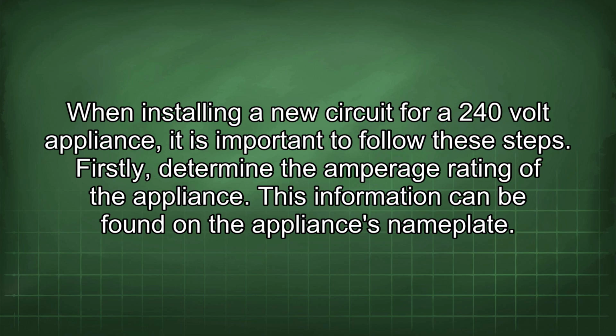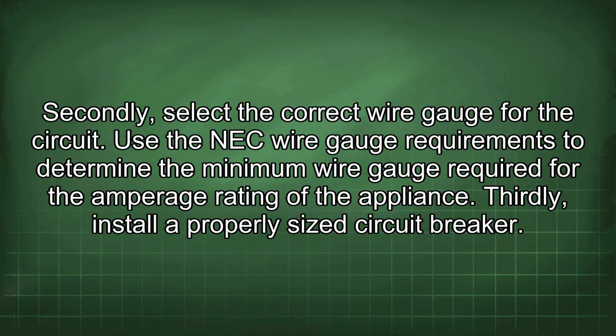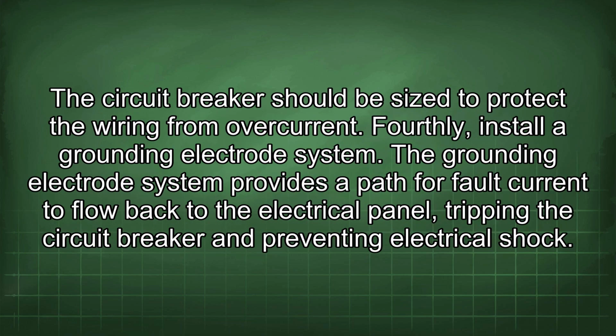Firstly, determine the amperage rating of the appliance. This information can be found on the appliance's nameplate. Secondly, select the correct wire gauge for the circuit. Use the NEC wire gauge requirements to determine the minimum wire gauge required for the amperage rating of the appliance. Thirdly, install a properly sized circuit breaker. The circuit breaker should be sized to protect the wiring from overcurrent.